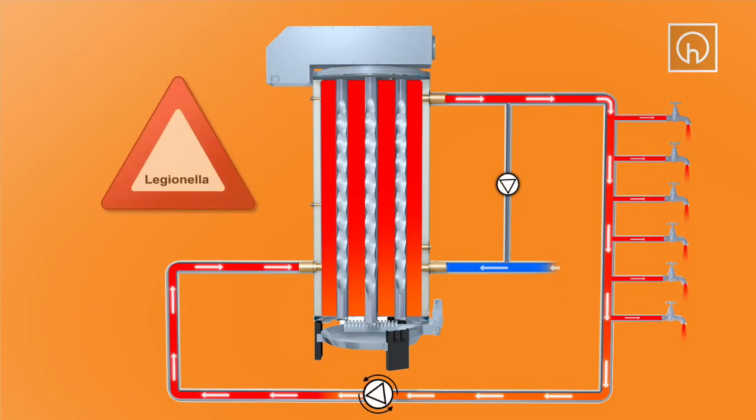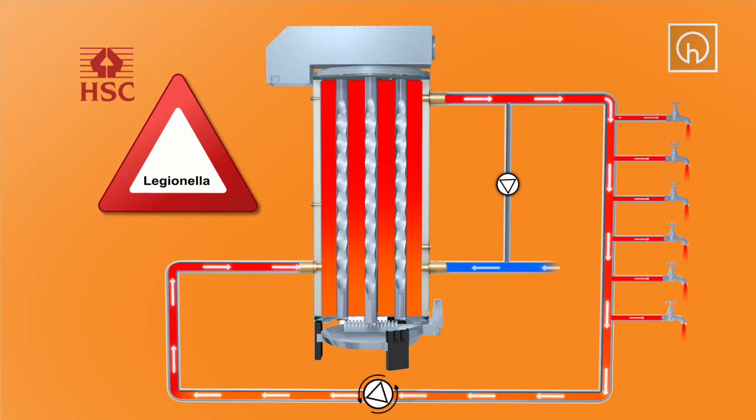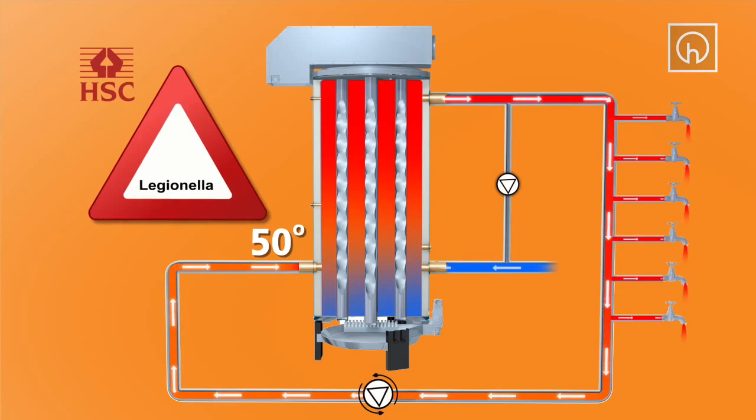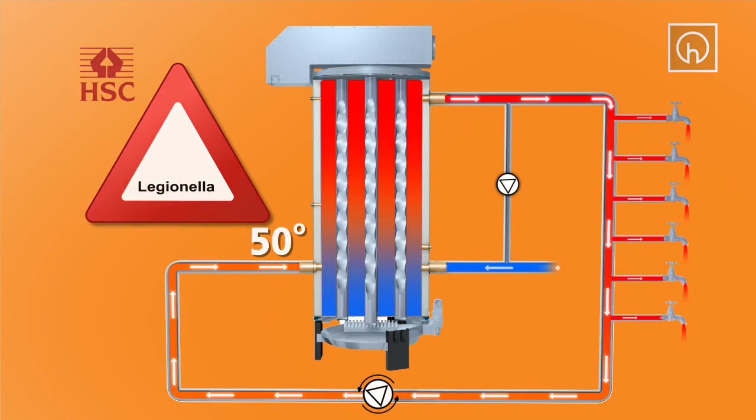For hot water to be safe from risk of Legionella, it is a requirement that the return temperature from the system is maintained above 50 degrees Celsius. In larger systems, it may be necessary to have a higher set point temperature to ensure this requirement is satisfied.